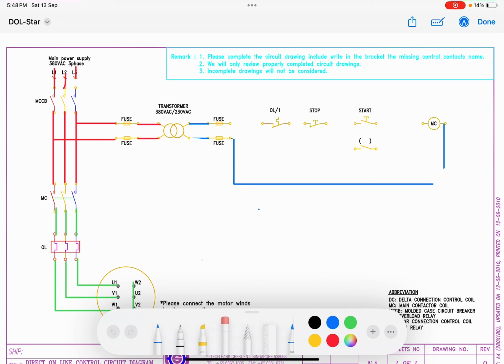Or, for easier understanding, we can connect the top line first. From the fuse, it is going to go to your OLR overload NC contact, and after the OLR, it is going to go to your stop push button NC contact, and after the stop push button it is going to go to your start push button contact.